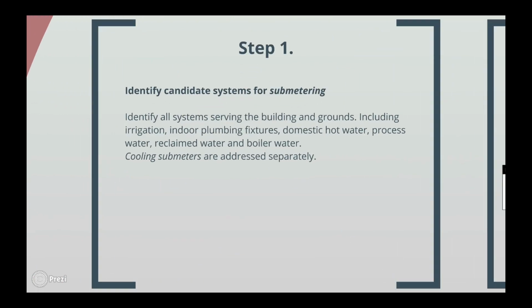Now let's talk about step-by-step guidance. Step 1. Identify candidate systems for submetering. Identify all systems serving the building and grounds, including irrigation, indoor plumbing fixtures, domestic hot water, process water, reclaimed water, and boiler water. Cooling submeters are addressed separately.